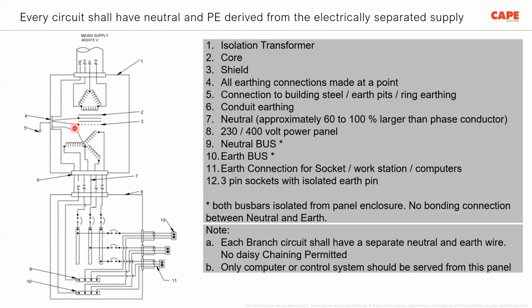For example, you have an isolation transformer. The incoming PE conductor and the outgoing PEs are all connected together in a bus bar. As you can see here, all earthing connections are made at one point. Then please note that the phase, the neutral and the earth to every socket are running parallel. We are not looping the neutral or the earth conductor. This is the correct way of providing power supply to computer or electronic installations.